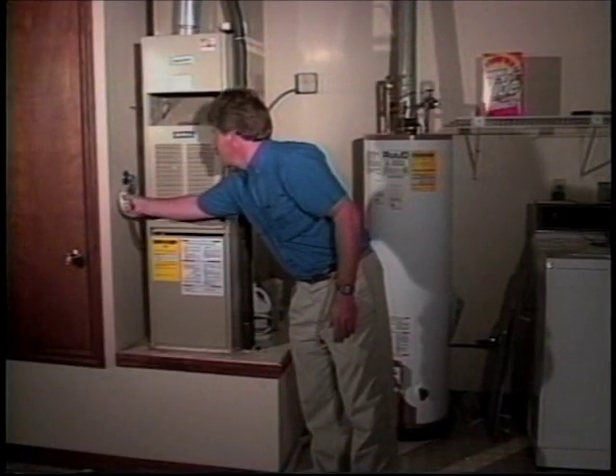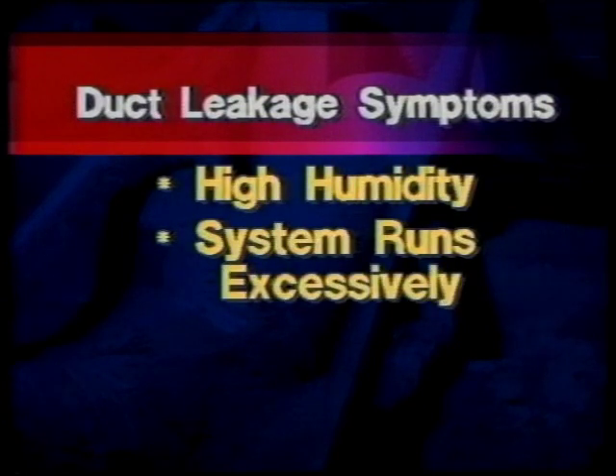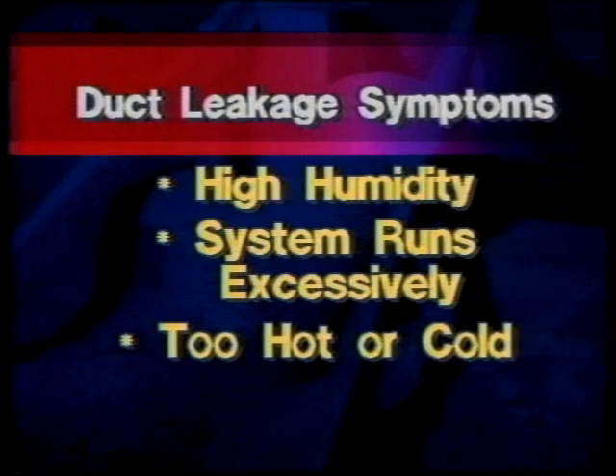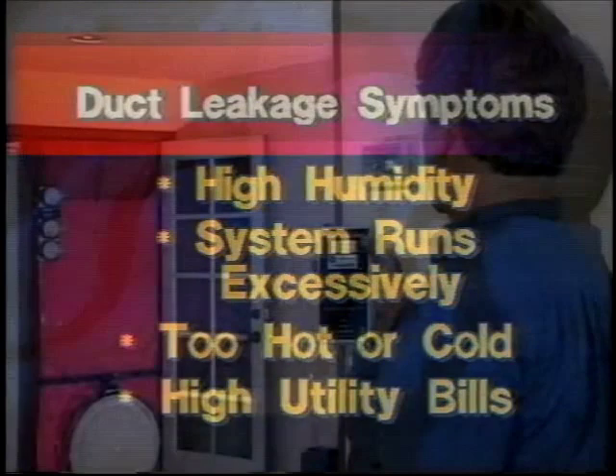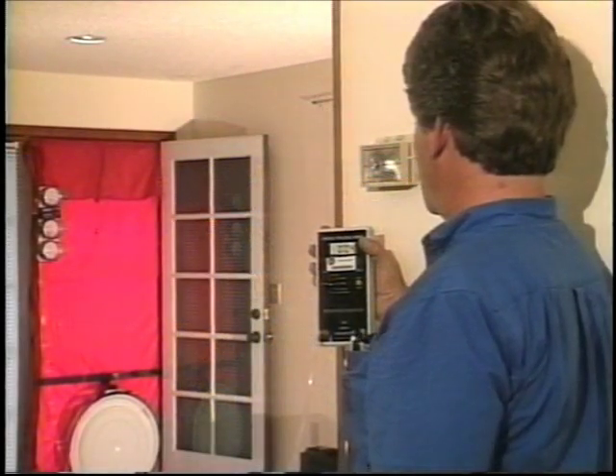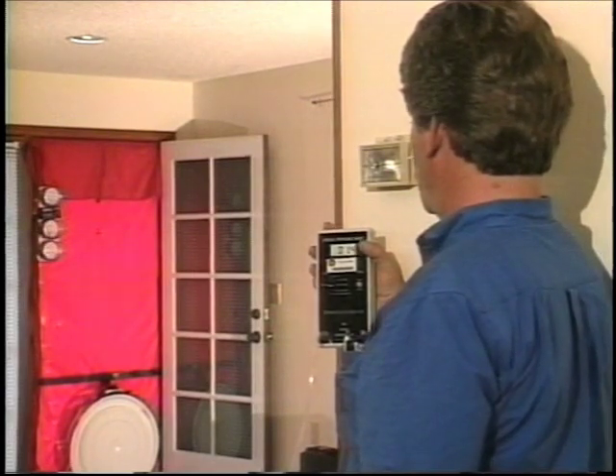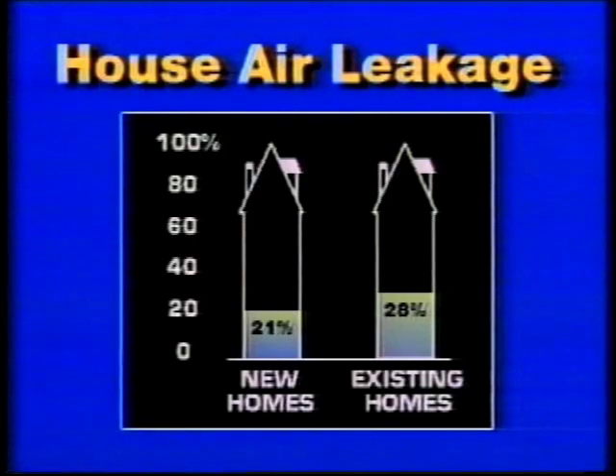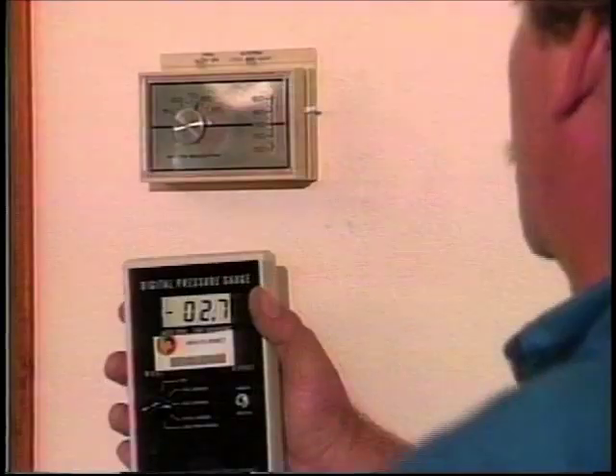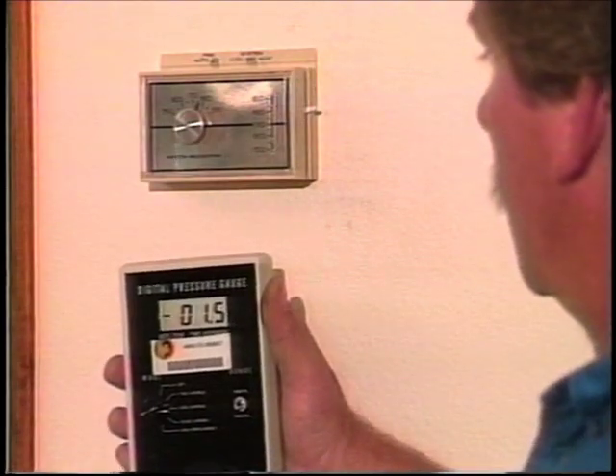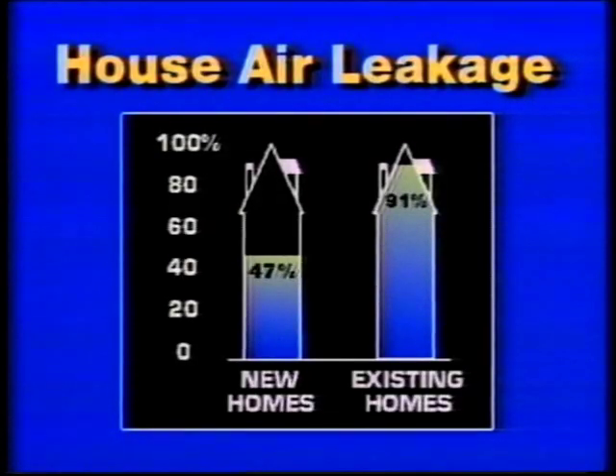Without specialized training, it is often difficult to know if you have a duct leak problem. The symptoms of major duct leaks include high humidity, the heating and cooling system running excessively, a house that is too hot or cold, and high utility bills. For the building scientist, one of the big clues of duct leakage is high infiltration. Natural infiltration changes about 25% of the house air each hour. When the central forced air system turns on, however, air infiltration increases by two or three times, indicating that duct leaks are pulling a lot of air into homes.